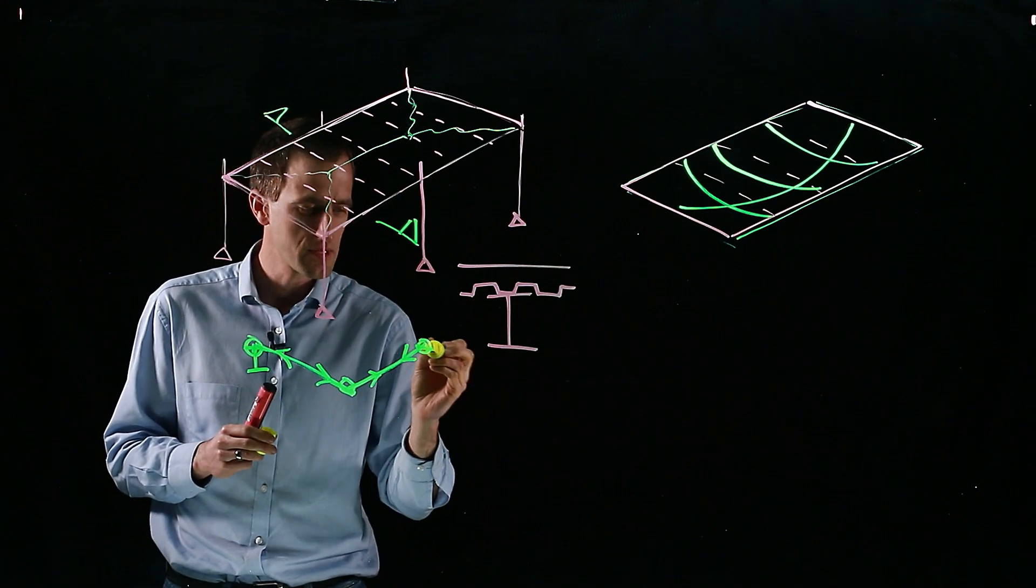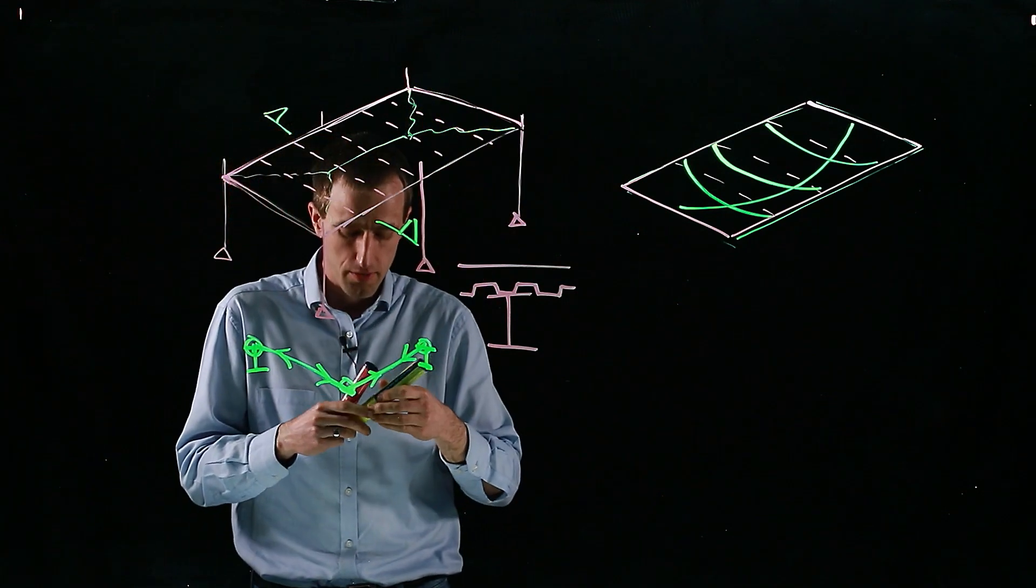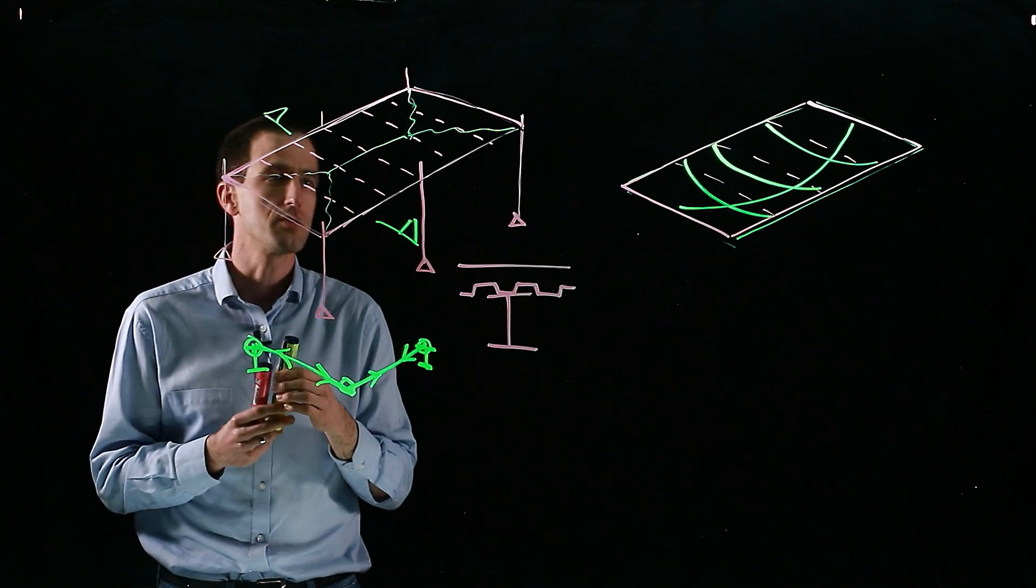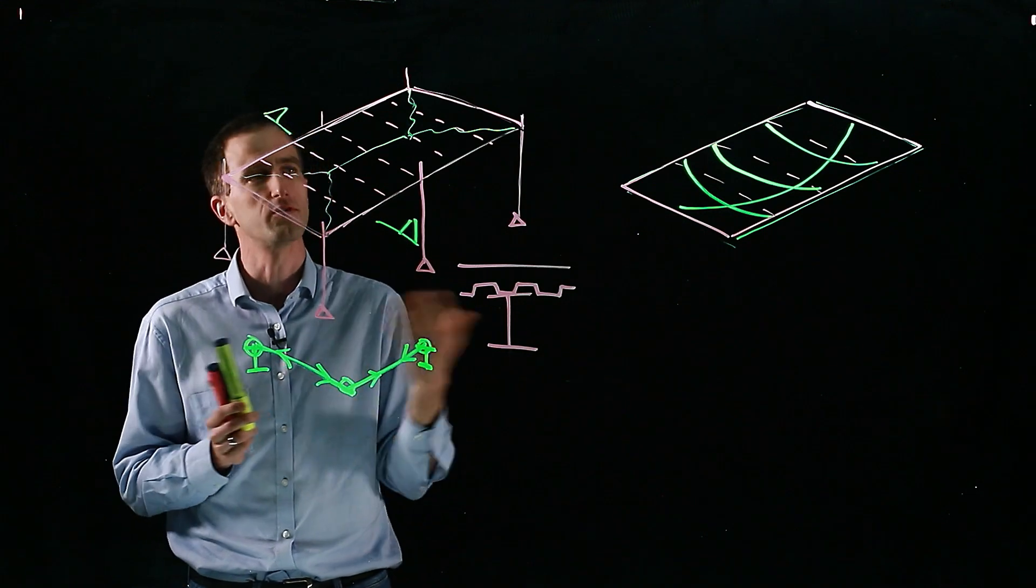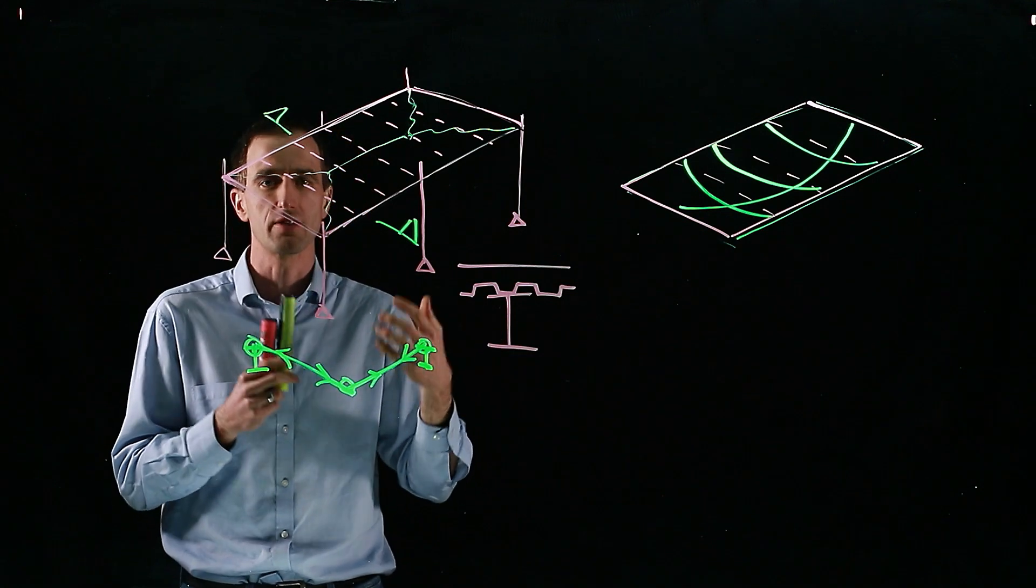Here my beams, I protect these, they carry it back through to the columns and down. So the useful thing about this is we can reduce the amount of passive protection we require by somewhere between 40 and 60 percent, saving a lot of money on design but still providing a safe system.